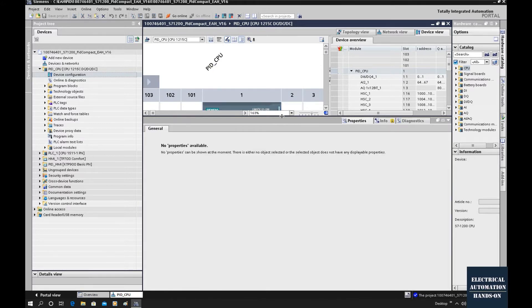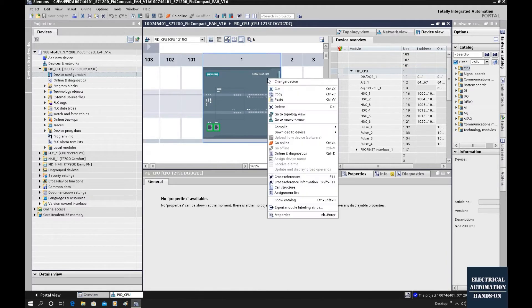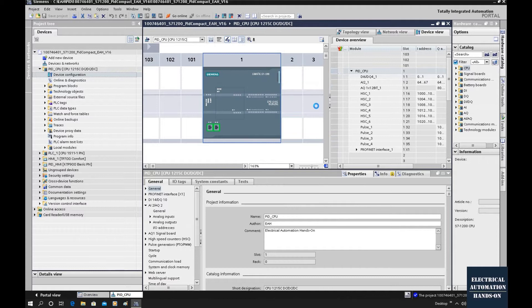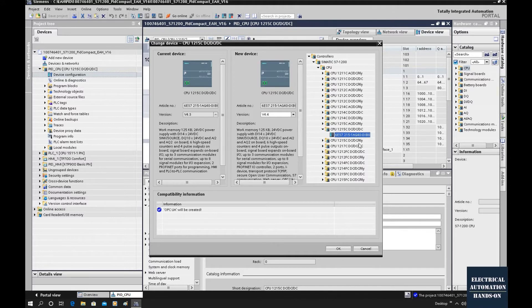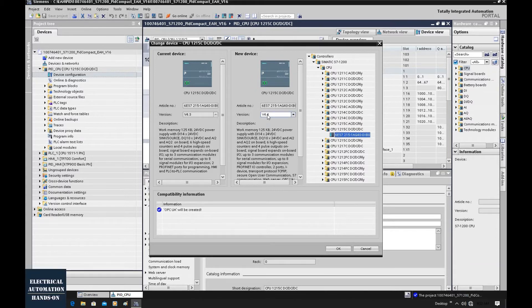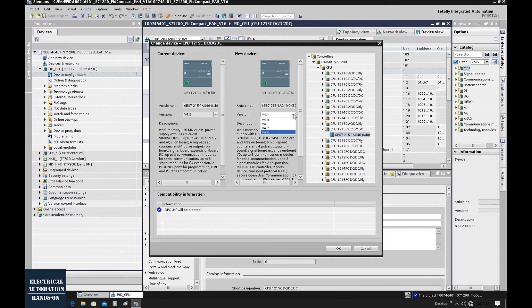Let me show how we can replace that. We can right-click and click 'Change Device'. Select the same type, that is CPU 1215. Find this controller — keep in mind, only version 4.4 from the S7-1200 series controller supports OPC UA server. So we need to change the hardware configuration from 4.3 to 4.4. Click version 4.4 and click OK.